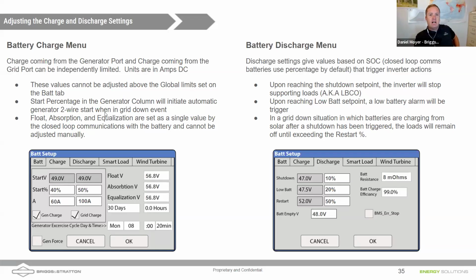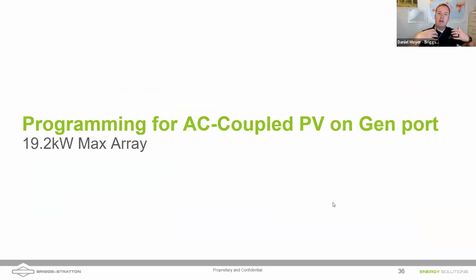Here we're setting the percentage at which we start a grid charge, the rate at which we charge from grid, and at what rate we charge from generator. These are the figures I mentioned earlier about the alarm, the shutdown, and at what percent we'd start the battery back up once recharged. That's a little different from activate battery, which is when we turn the loads back on.